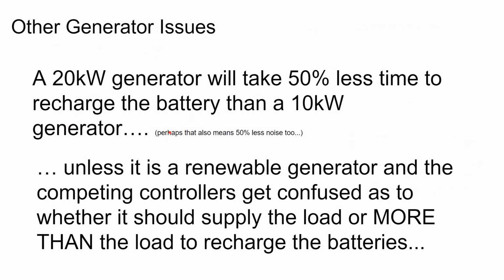Some other things to think about with generator selection: a larger generator, a 20 kilowatt generator, will take 50% less time to recharge the battery than a 10 kilowatt generator. It might be a little bit noisier, but the runtime is less. Usually the customer doesn't want to hear it, so going with a noisier solution that only runs half the time might be the better option.